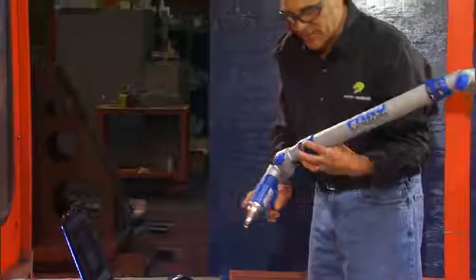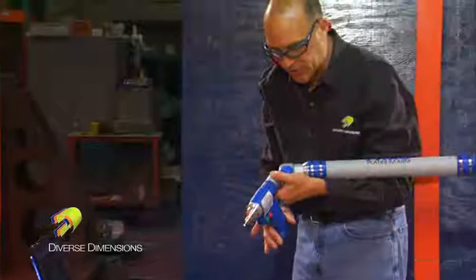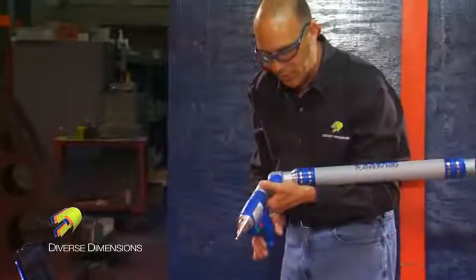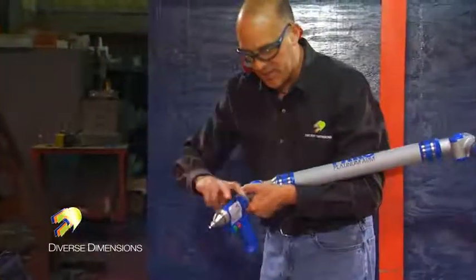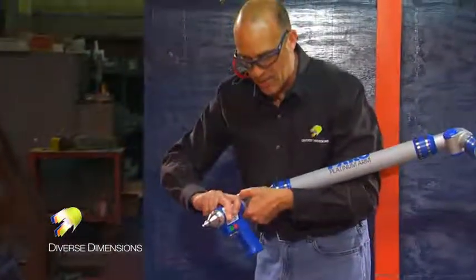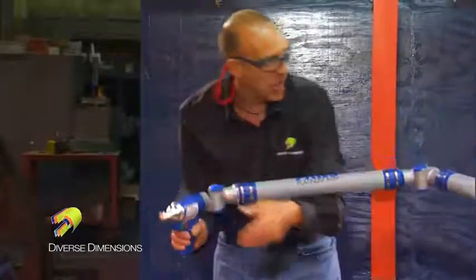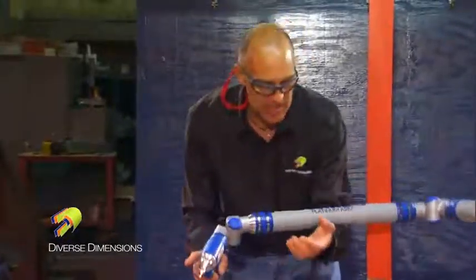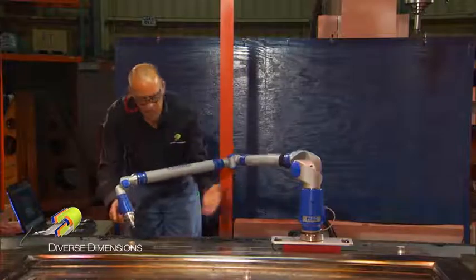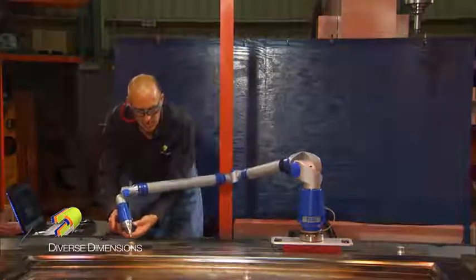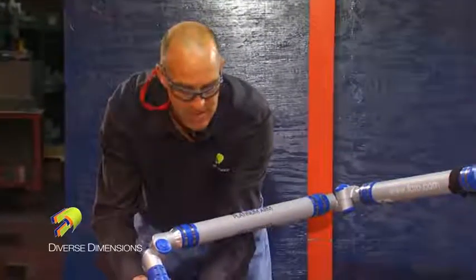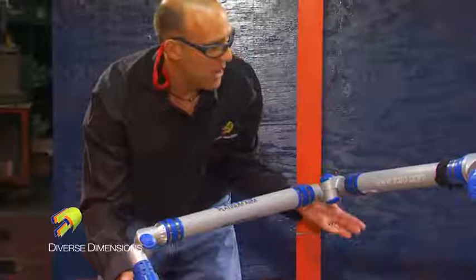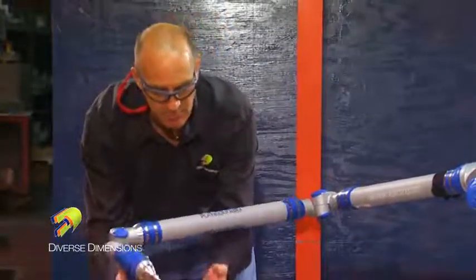I've got a 7th axis on my arm here which is this trigger or this pistol grip. If you've got a 6th axis you'd be grabbing right around here. What I usually like to do is I like to have the cone, our calibration cone, a pretty healthy way away from the arm base. And then I usually let the arm just rest here like this since it's counterbalanced.